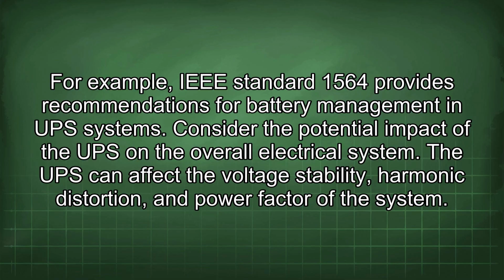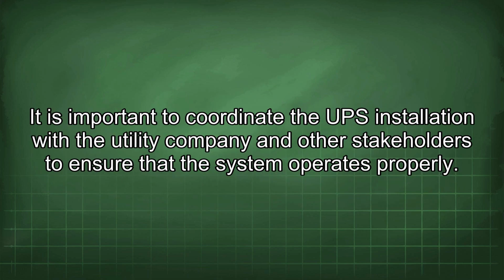Consider the potential impact of the UPS on the overall electrical system. The UPS can affect the voltage stability, harmonic distortion, and power factor of the system. It is important to coordinate the UPS installation with the utility company and other stakeholders to ensure that the system operates properly.